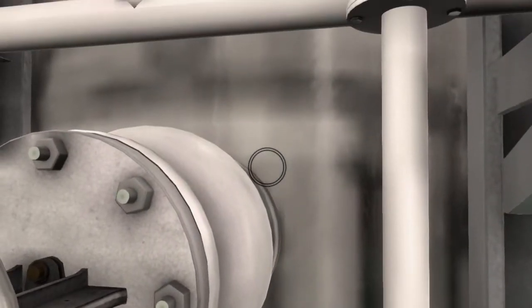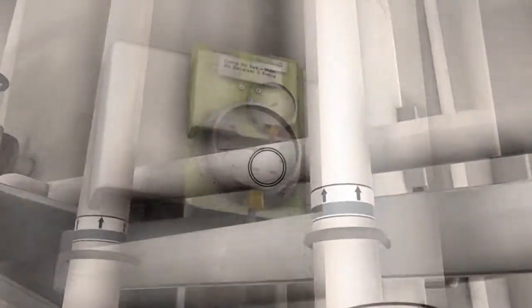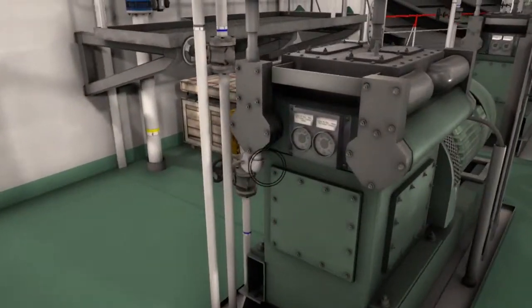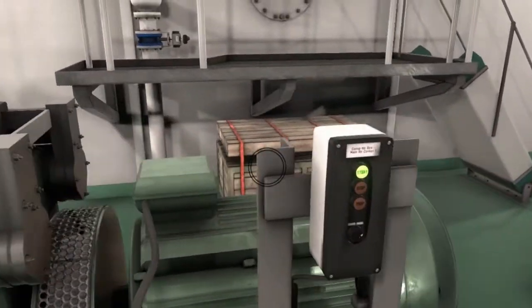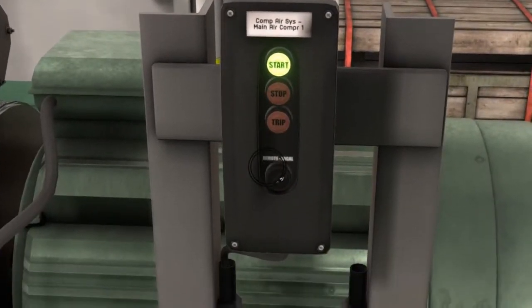Then let's go monitor the charging pressure of the air receiver if it's really filling up. If it's steadily charging, let's go back to the compressor and switch it to remote operation. The compressors will automatically stop when it reaches 30 bars and starts based on the priority setting of the logic controllers.